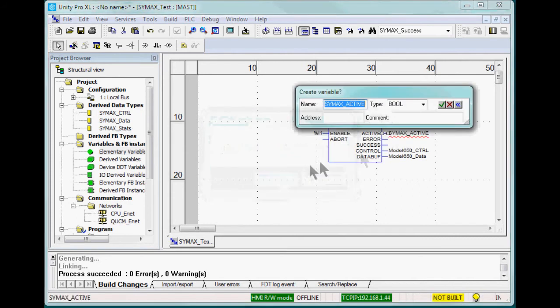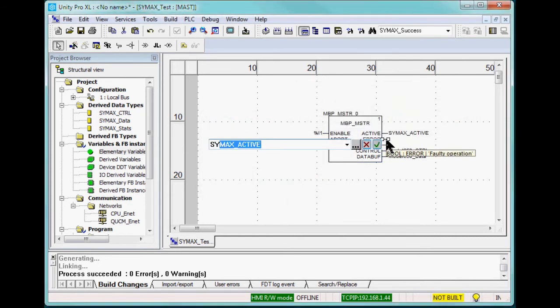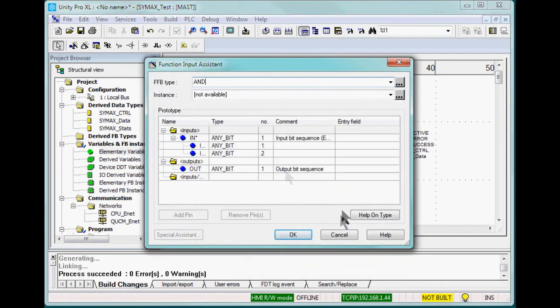We are now going to add some more logic to make it behave better and to get more of an idea about what is going on. Binary variables for active, success, and error are used to latch the MSTR on until it succeeds or fails.